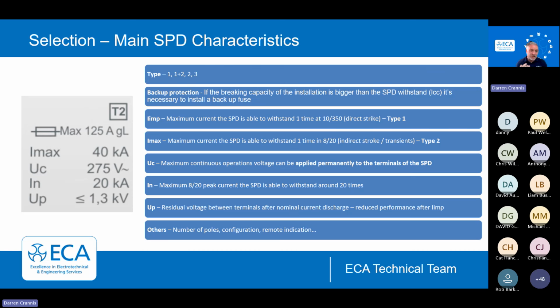Uc, that's when these things start conducting. So if you think you're going to use an SPD for voltage control to get your voltages down in your grid, no, speak to your grid. Look at things maybe like voltage optimization or UPSs. That's the only thing that can condition your voltage. These will only start conducting at 275 volts and above. So we are looking at those big surges.